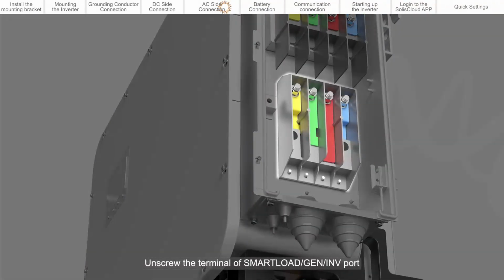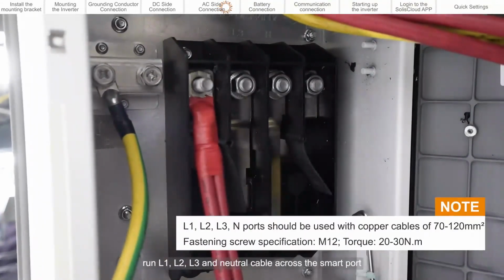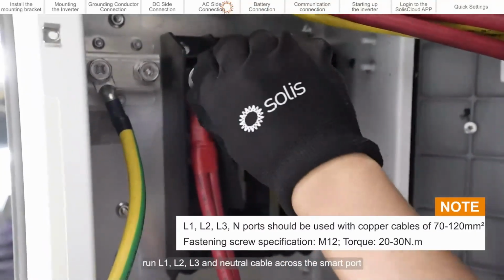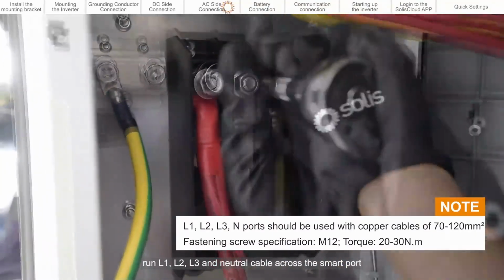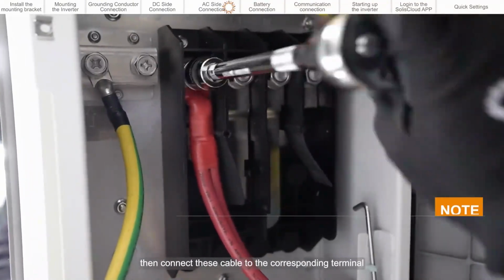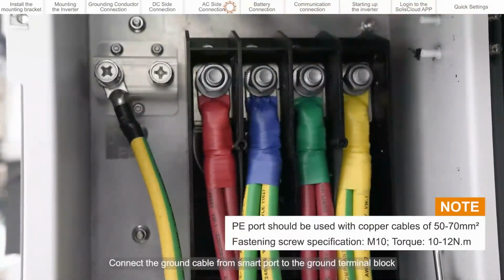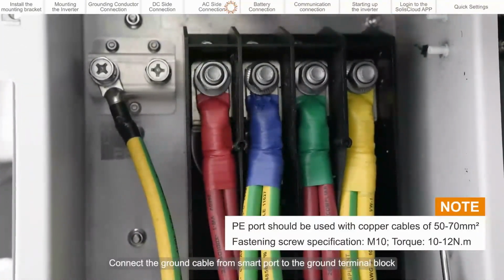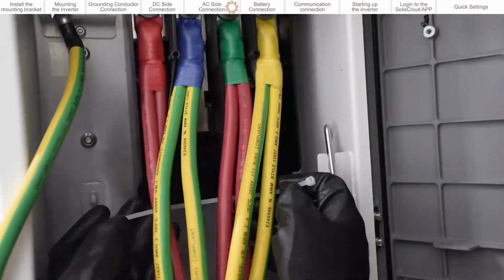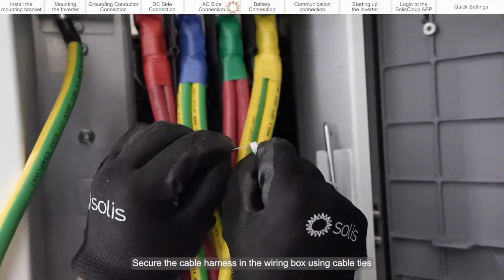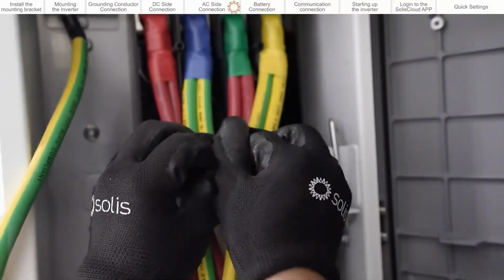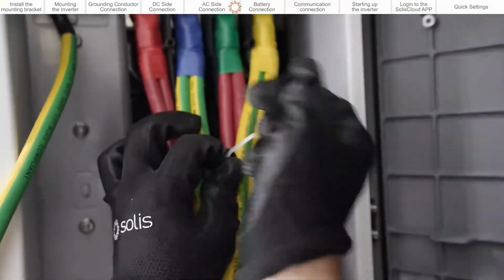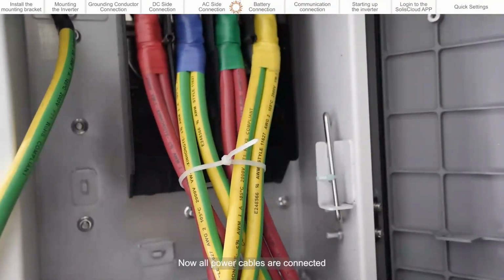Unscrew the terminal of SmartLoad/GEN/INV port. Run L1, L2, L3, and neutral cable across the smart port, then connect these cables to the corresponding terminal. Connect the ground cable from smart port to the ground terminal block. Secure the cable harness in the wiring box using cable ties. Now all power cables are connected.